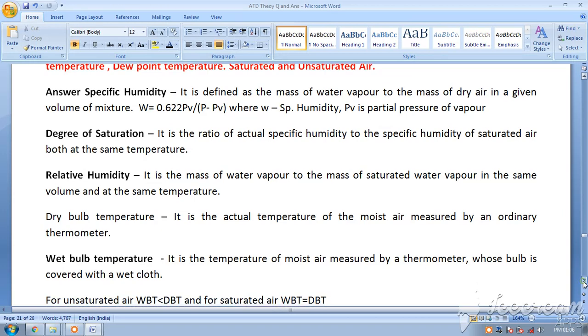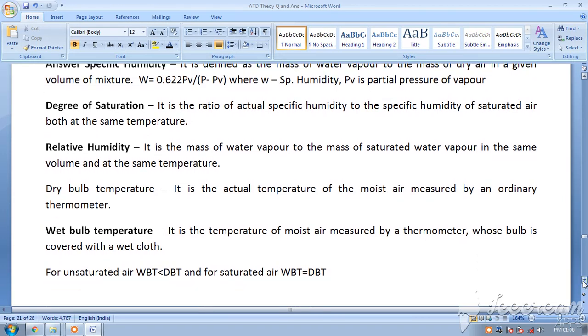Wet bulb temperature uses the same thermometer, but a cotton wick is tied to the bulb where the mercury is, and that wick is submerged in water and saturated with it. The thermometer is then rotated, and whatever temperature is obtained is the wet bulb temperature. It is the temperature measured by a thermometer whose bulb is covered with a wet cloth. The wet bulb temperature is always less than the dry bulb temperature for unsaturated air, but if the air is fully saturated, the two temperatures are equal.